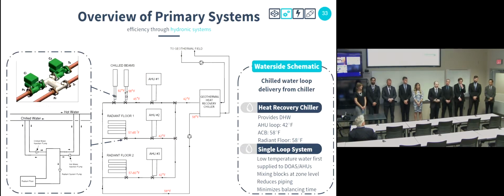At the chilled beam zones, we utilize TACO's low flow mixing blocks. These use zone level pumps to regulate the temperatures in the chilled beam zones, allowing us to maintain our desired temperature. At the radiant flooring systems, we use injection pumps to inject hot and cold or chilled water from the desired loop into the radiant system loops, and the radiant system circulation pumps then keep that temperature at our set point. And the single loop system, because it uses zone level circulation pumps, also reduces the balancing time required once the system has been finished.